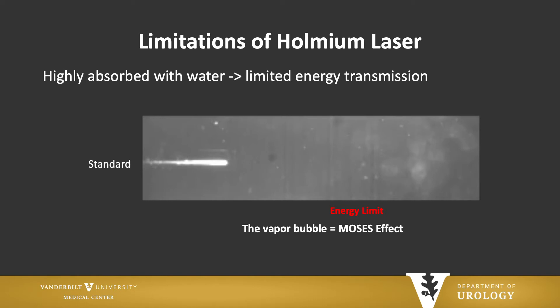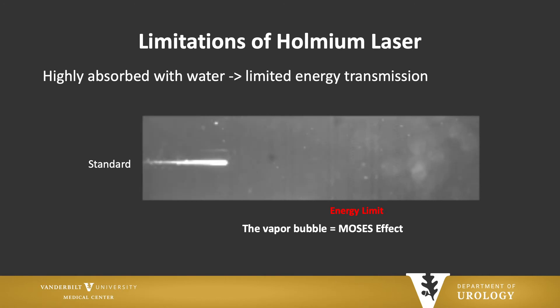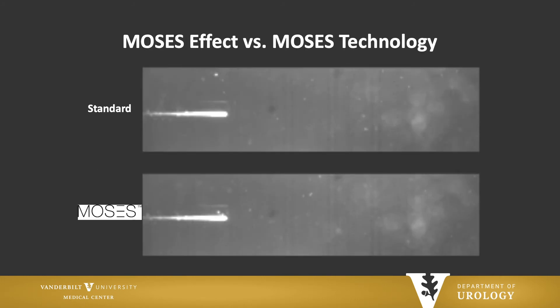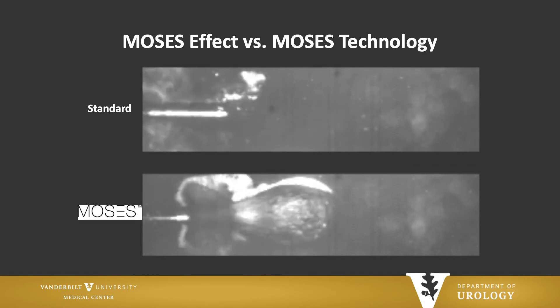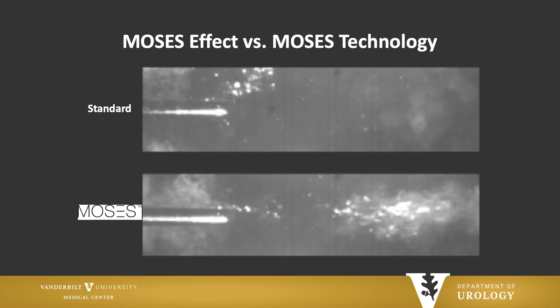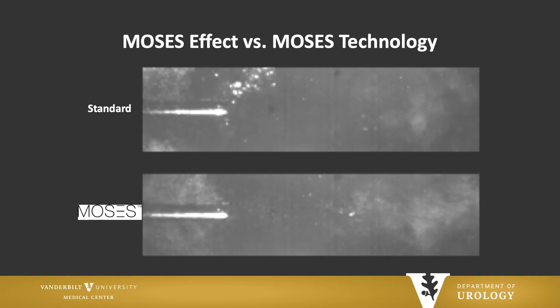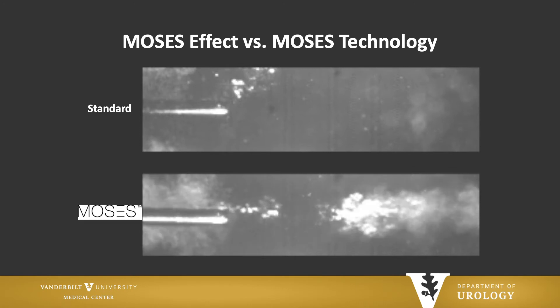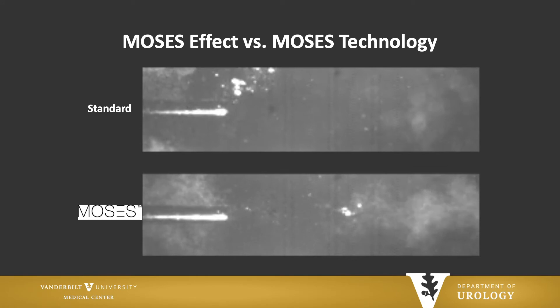There are limitations to the Holmium laser. It's highly absorbed by water, but that limits energy transmission to the stone. The Moses effect was described in 1986 in endovascular tissue ablation — it refers to the creation of a vapor bubble at the tip of the laser fiber when firing, and then the laser pulse travels through that bubble. Moses effect is different from Moses technology. Moses technology actually modulates the laser pulse to exploit that effect: a small initiation pulse pushes fluid aside, allowing the second pulse to travel through it and deliver more energy to the stone.